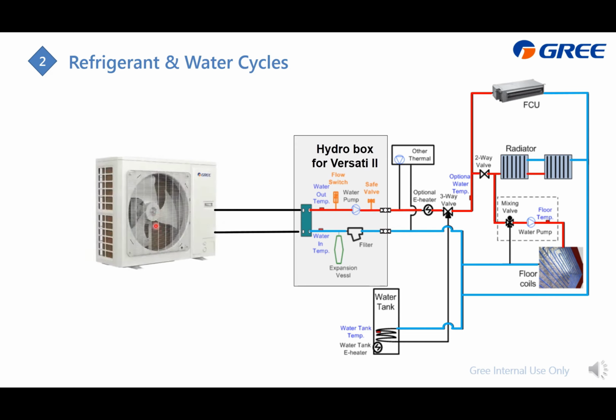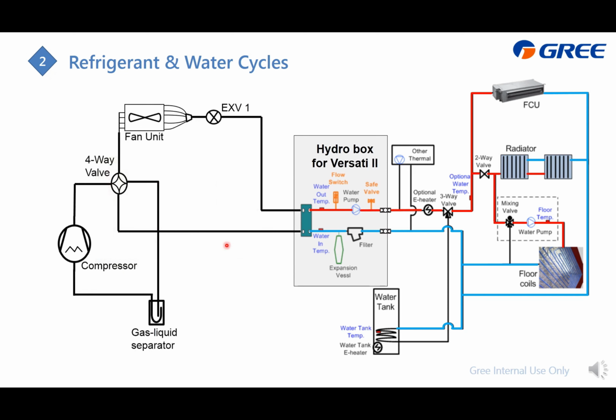As for this part, this is the outdoor unit, which is this one. You can find that we have the compressor, four-way valve, outdoor heat exchanger, EXV, and also the gas liquid separator. And here is how the refrigerant flows in heating mode. Sending out from the compressor, it is hot and high pressure. Then it goes to the plate heat exchanger to release heat to heat up the water. Then the refrigerant becomes liquid and goes to this EXV to get expanded to become low pressure and low temperature liquid. Then it absorbs heat from this outdoor heat exchanger to become gas and goes through this four-way valve. Then it goes to the gas liquid separator. After that, 100% gas will get into the compressor to be compressed.